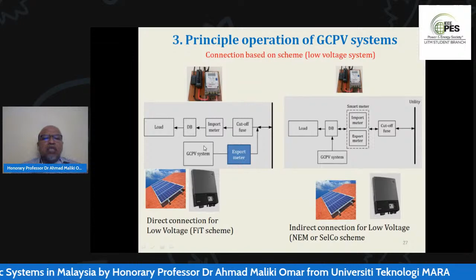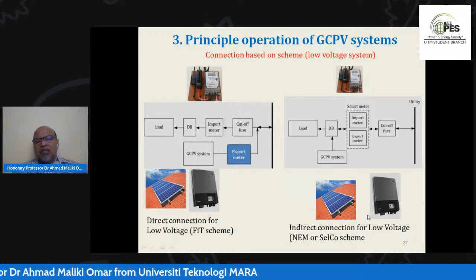If you look at the connection on a low voltage scheme, this is the FIT scheme just now, based on NEM or SelCo. And this is how we connect for the medium voltage system, especially in a factory, where the incoming is 11 kV. We don't connect to the 11 kV except for the FIT scheme — for that we need to connect direct to 11 kV. But for NEM and SelCo scheme, we need to connect to the DB, which is very close to the load.